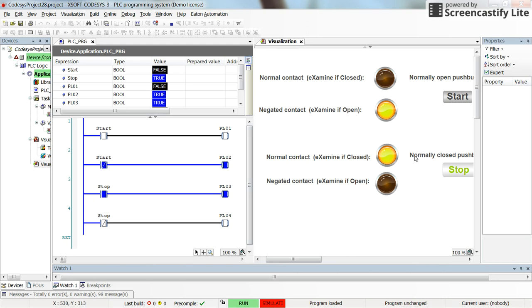However, if you use a normally open push button for the stop as well, then in that case we need to use an examine-if-open contact or negated contact in the code, because as long as we don't press the push button we want logic continuity. It's the other way for the start push button — if it's a normally open push button, which is usually the case, in the code we use a normal contact for that.